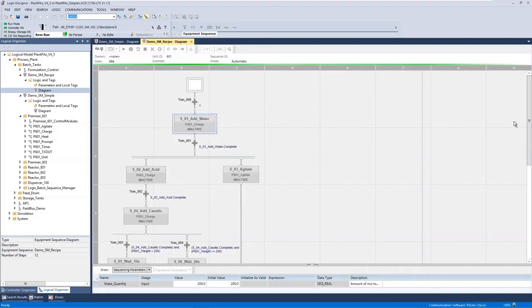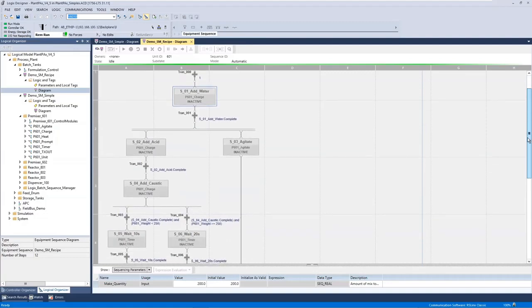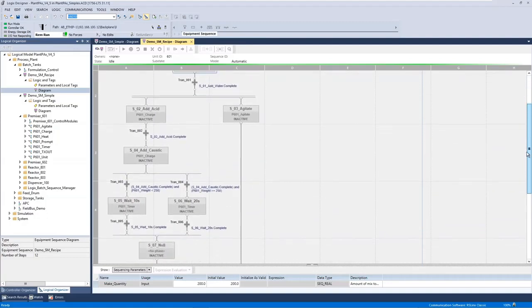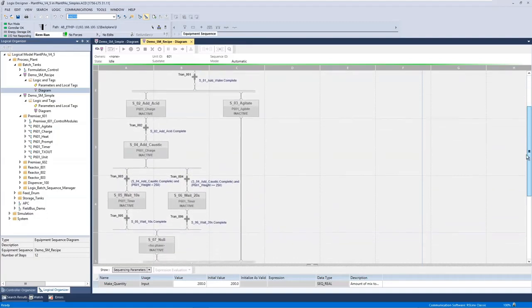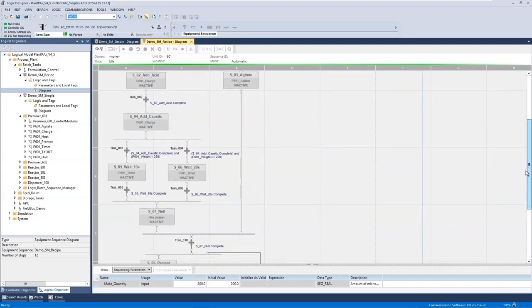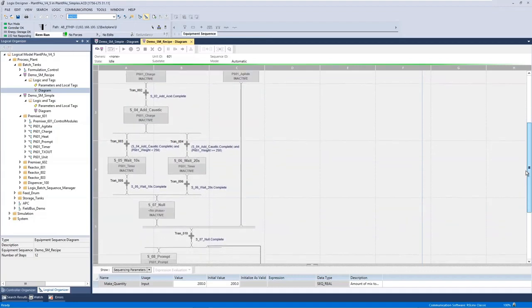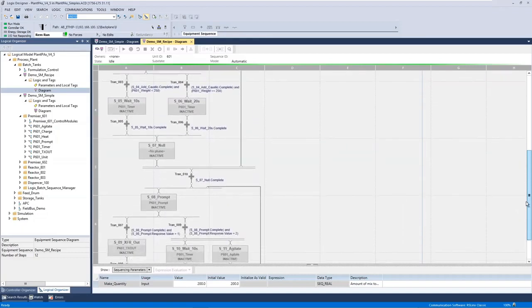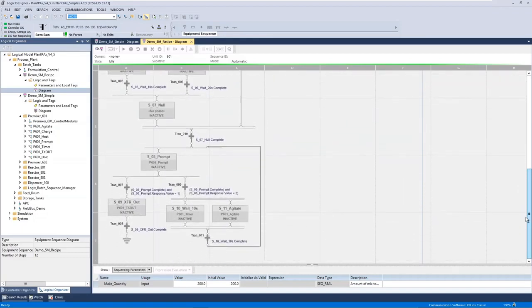Here is a more complicated example where again we're running a charge phase to add some water, but now running a recipe with steps in parallel — agitating, adding acid, adding caustic, mixing for an amount of time based on the weight in our reactor, and prompting the operator what we'd like to do. Based on the response, either transferring out our mixture to the final storage tank or mixing for a further amount of time and then asking the operator again.